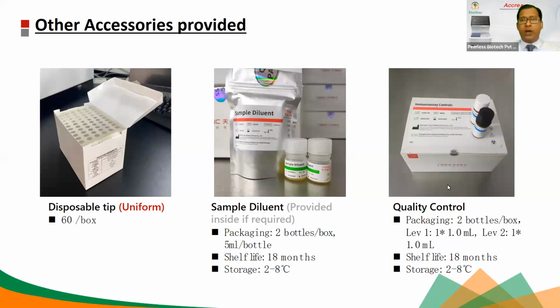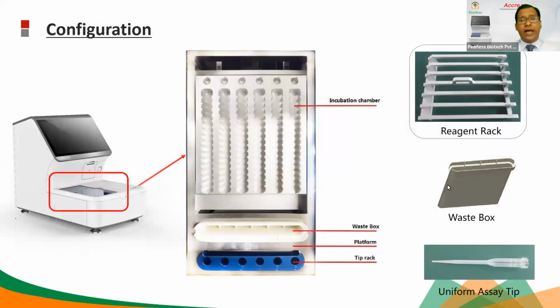Now, going forward, this is the configuration. This is the instrument, and this is the incubation chamber, waste box, and tip rack. And we are using a uniform tip. That means the same tip will be used for all the tests like T3, T4, TSH, AMH, troponin. So tips are not different. Some other companies have different tips for different assays, so the customer has to keep a different inventory. As a distributor, you also may need to keep a different inventory. Here it is not like that. Kits are similar for all the assays, so there is no problem.